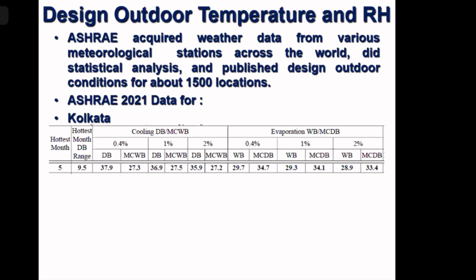The dry bulb temperature is 36.9, and corresponding to that we have to consider a wet bulb temperature, which we call mean coincident wet bulb temperature, 27.5 degrees centigrade. ISHRAE has collected data from various meteorological stations and made a statistical analysis of dry bulb temperature and found out the temperature which is included within 99% of the time. That is 1% occurrence level.